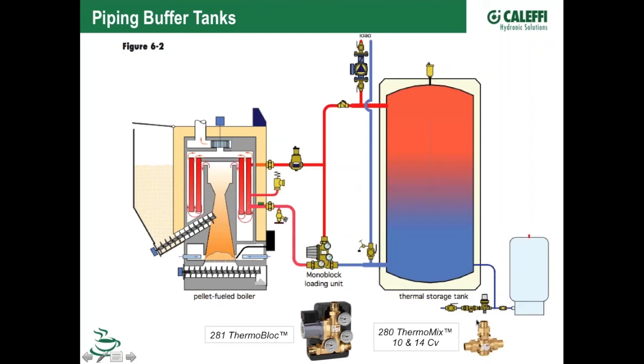We offer it as a standalone without the pump on it here in a 1 inch and 1 1/4 inch version. This has, I think, a Star 16 pump on it, so you're limited to maybe a 10 gallon per minute flow. Let's say you've got a job where you need a 15, 18, 20 gallon per minute flow. You can buy the valve as a standalone piece and then put your own pump on it here. You can see real high CV on that valve, so we've got plenty of flow rate. We've got wide open ports in that. That is also available with a couple different temperature sensor cartridges in the bottom of there.